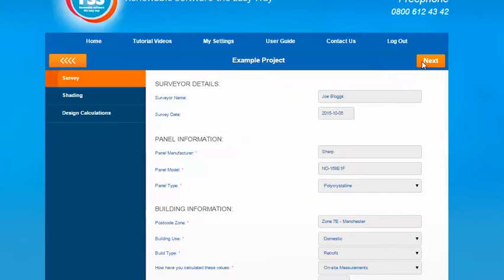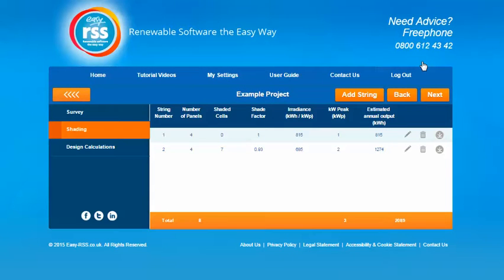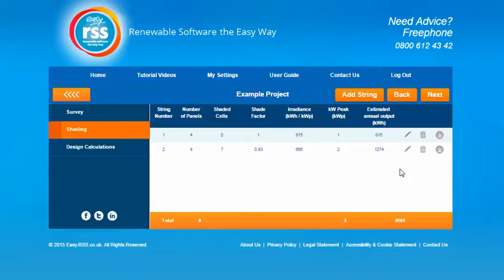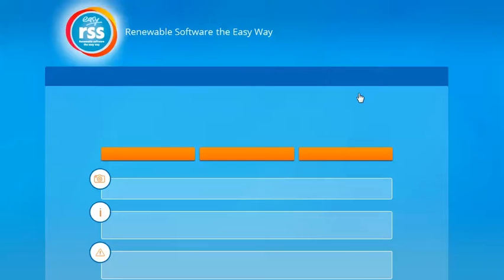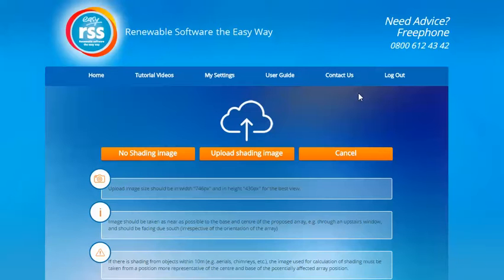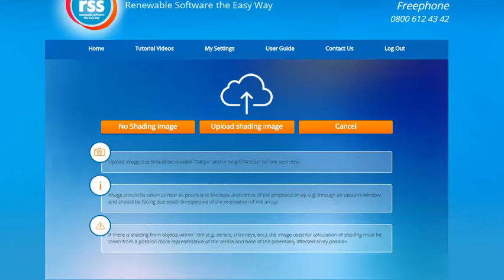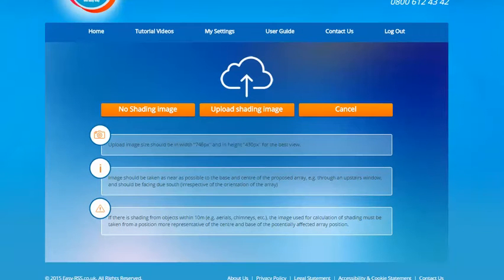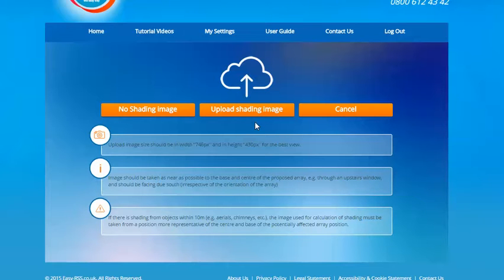Once you've completed all those sections press the next button so the information is saved for you. You then have an option to add some strings which will allow you to do the shading analysis. We've added two examples here already. To add a new string, the initial stage is to select whether you have a shading image or no shading image. If you do have a shading image you can upload it in this section and it will sit behind the sun path diagram to help your analysis. If you are using an image it should be taken from as close to the base of the array as possible.